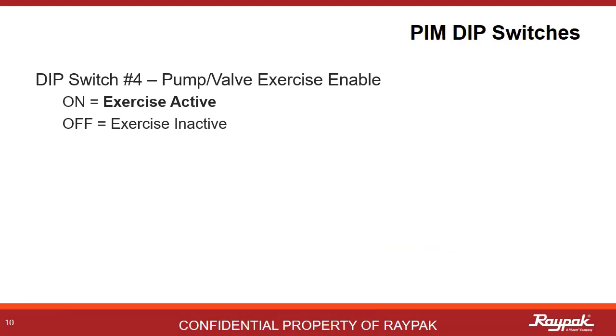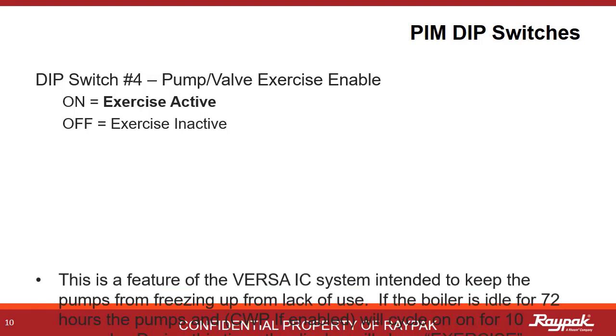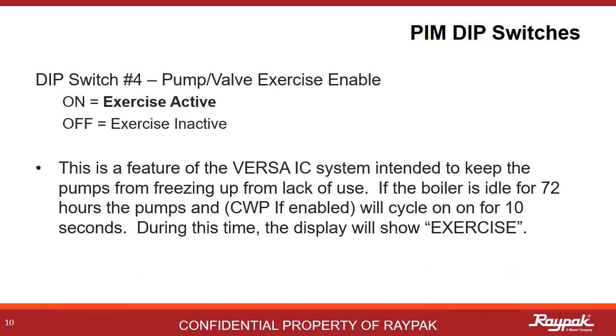PIM dip switch number four is an example of some helpful Raypak engineering. With PIM dip switch number four on, the boiler will cycle the pumps and cold water protection if present after a period of 72 hours of inactivity. So say you're in shoulder weather like spring or fall and you get a week of warm weather where the boiler does not need to fire — you don't want the pump to seize up from inactivity, so this system helps to prevent that. After 72 hours, the pumps will run for just 10 seconds to keep things working properly.